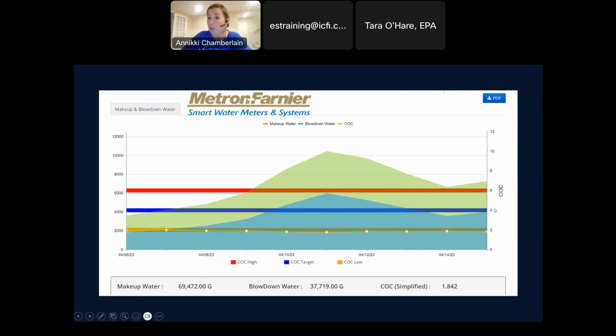So on the secondary axis is my cycles of concentration, and my target, which is 4. The red is my high threshold. Anything over that, I probably have a mechanical failure. And then 2, anything below that, I probably have a mechanical failure. And then here's my stats down at the bottom, the makeup, blowdown, and cycles for that time period. So these guys are running at pretty low cycles. Could be an operational setting, could be a stuck open blowdown. But what I know is if my target is 4, now I can start using this information. If my target's 4, and I'm running at 1.8, we'll just round up to 2, and that's about 70,000 gallons for that time period.